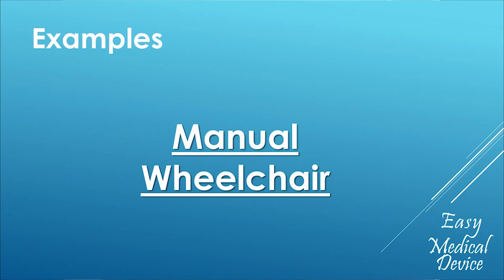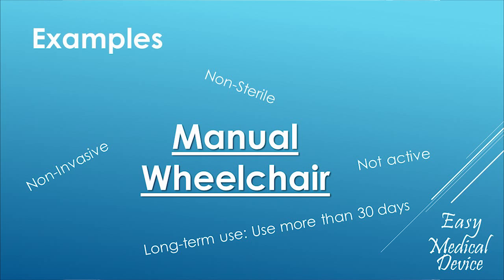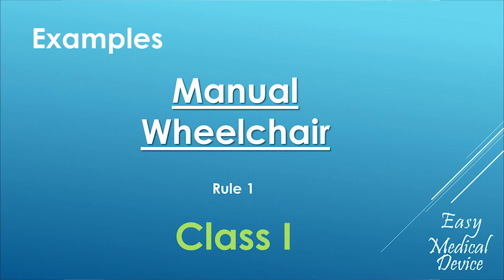Now we know how many classes there are, the parameters to take into account, and the 22 rules. Let's do a small exercise to see if you really understand how to classify a medical device. Starting with an easy one: the manual wheelchair. Some hints: it's non-invasive, non-sterile, non-active, and long-term use — more than 30 days. The answer is Rule 1, Class 1.